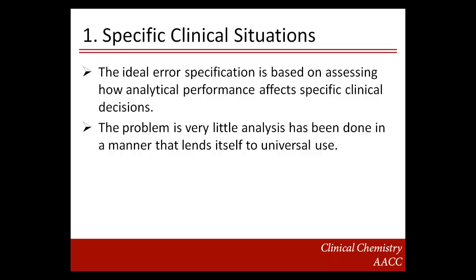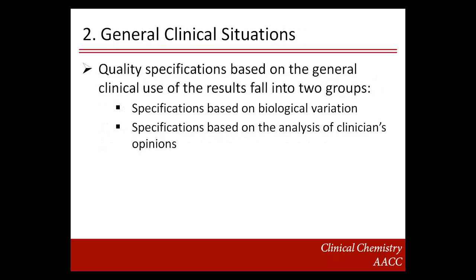Quality specifications in specific clinical situations are designed based on assessment of analytical performance in specific clinical situations, but very little analysis has been done to specify error criteria for universal use. Quality specifications based on general clinical use fall into two categories: specifications based on biological variation and specifications based on analysis of clinicians' opinions. Specifications based on biological variation are firmly based on medical requirements. Dr. Callum Fraser explains why it's important to set quality specifications based on biological variation, describing the effects of within-individual and between-individual variation.